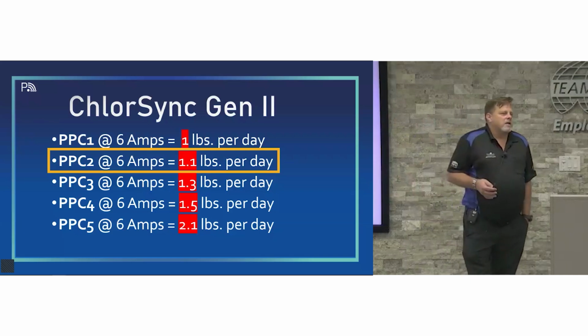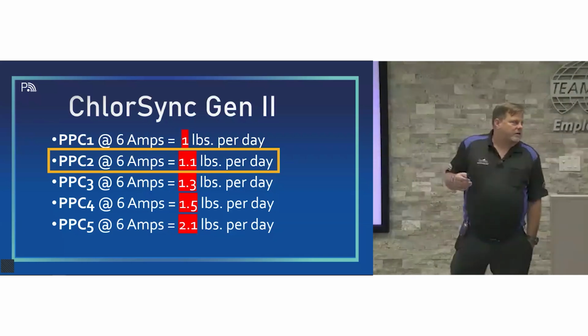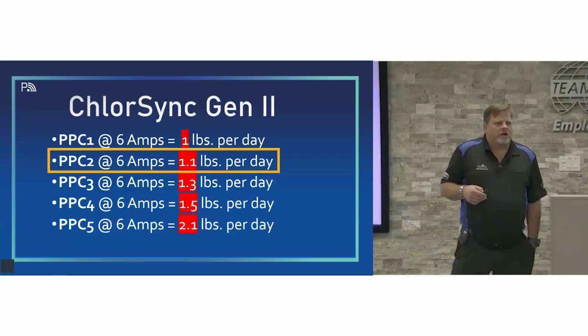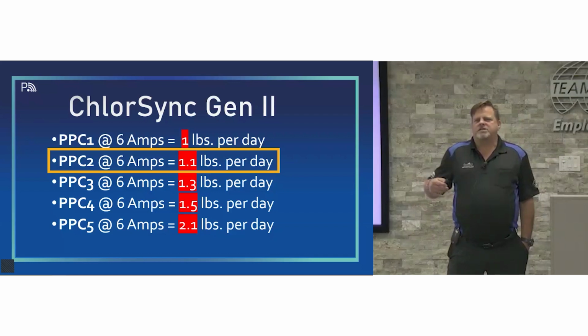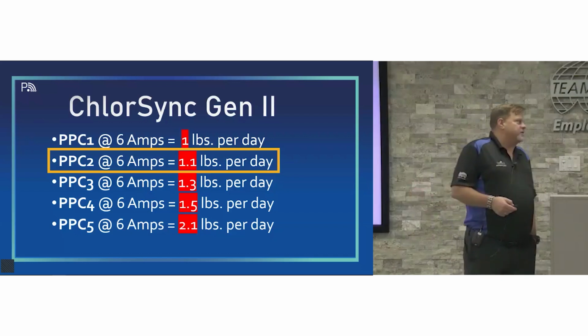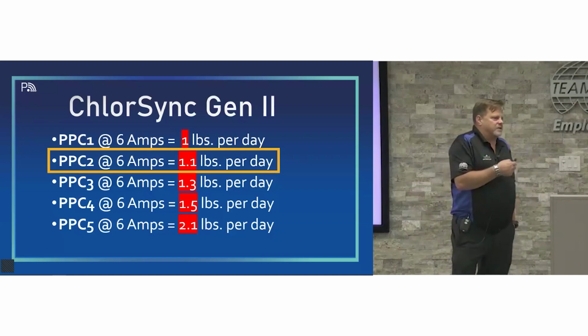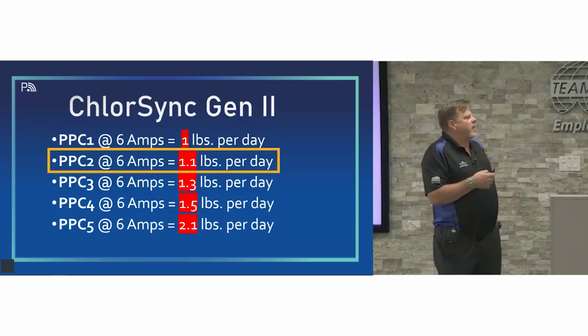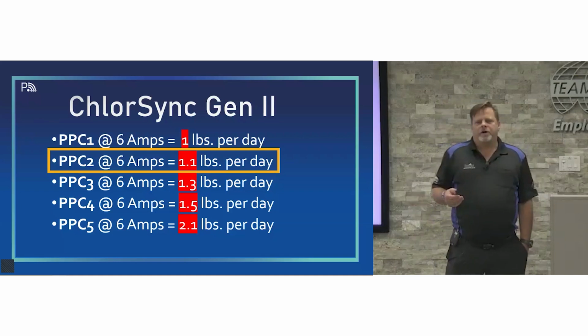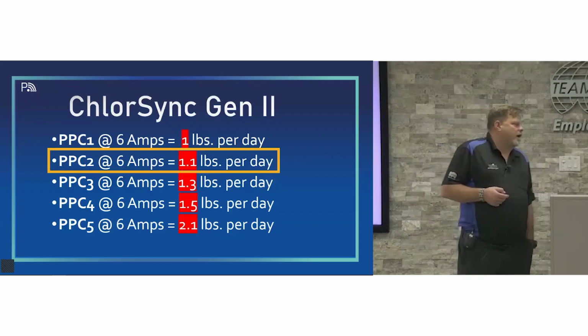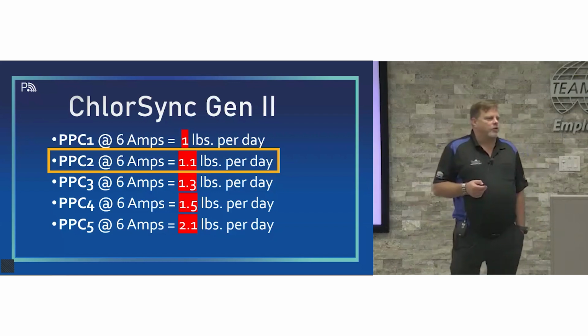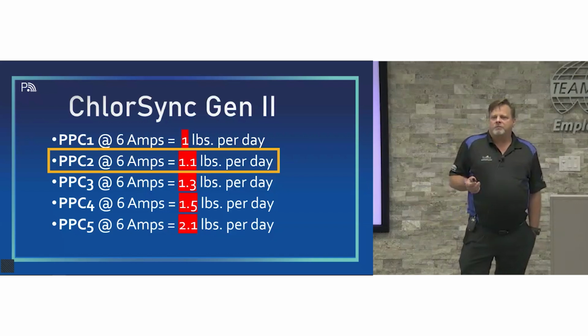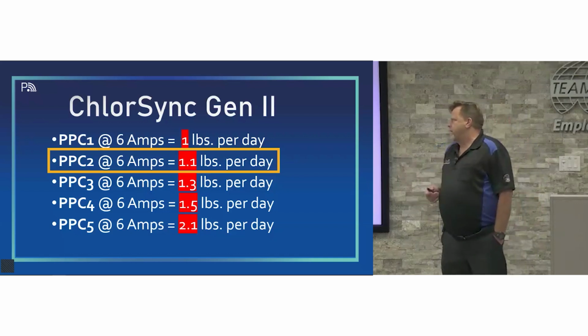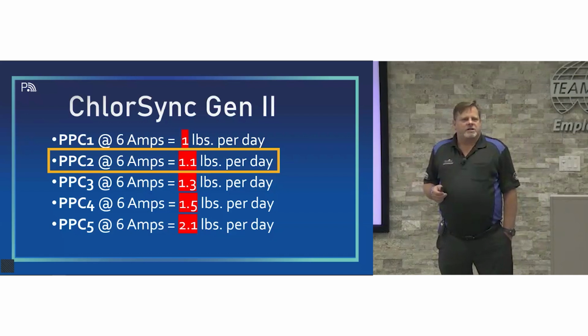All right, so when it comes to sizing, you'll see it advertised: this cell does this many gallons, this cell does this many gallons. This is the way I prefer to size a system, knowing how many pounds of chlorine it will generate in a 24-hour period. By knowing that, you can calculate whether that cell is large enough to do the pool you're doing. By simple math, you can break down how much chlorine that system can produce in 24 hours, down to 8 hours, down to 6 hours.